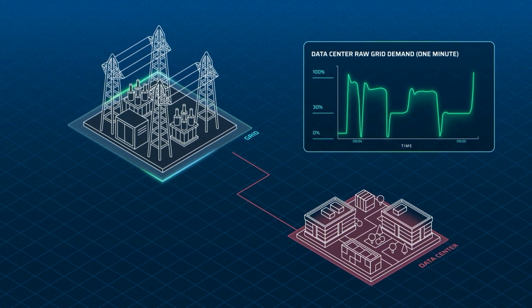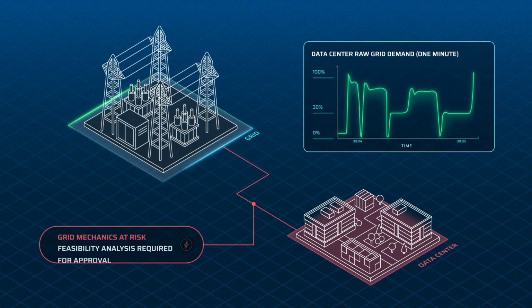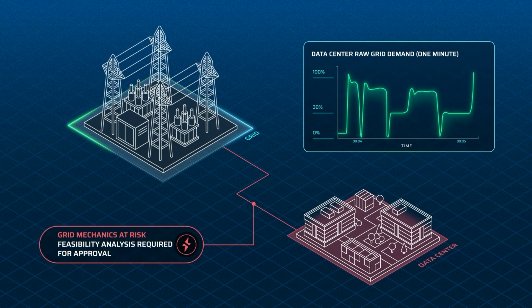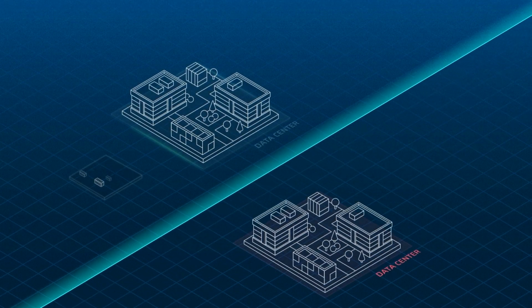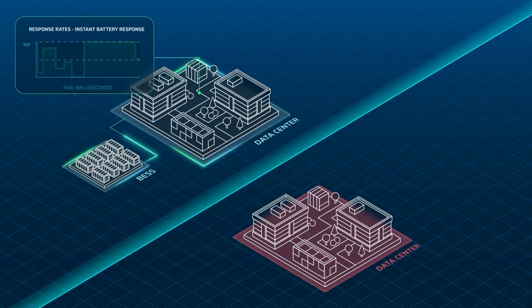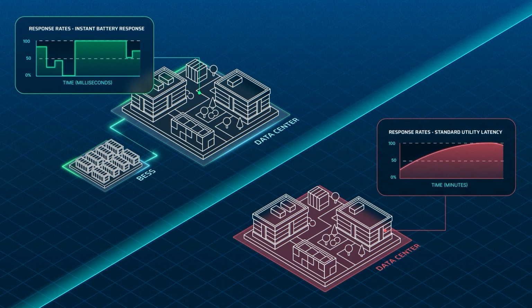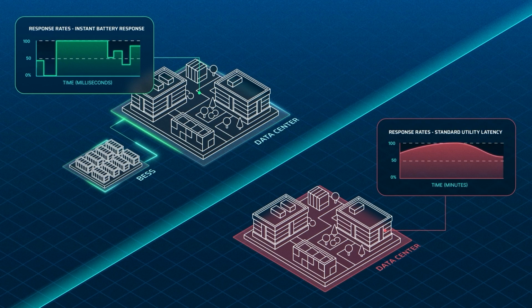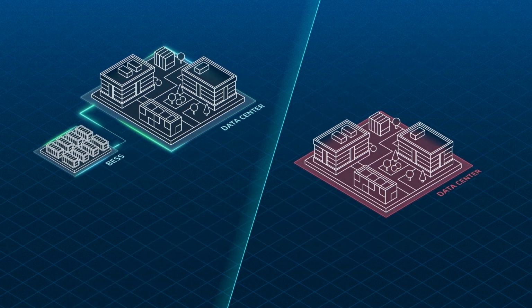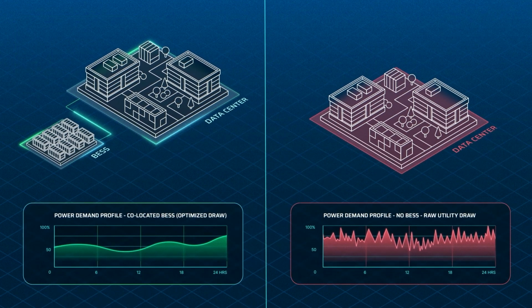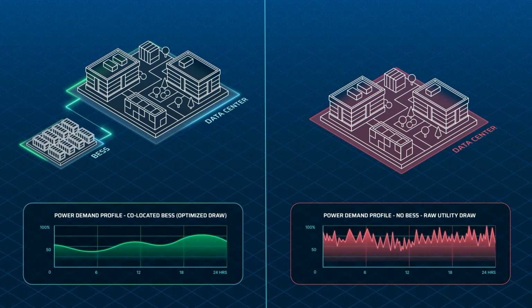This instability doesn't just affect the facility, but also threatens the mechanics of the local grid. This is why utilities are often reluctant to approve massive, volatile loads without first undertaking time-consuming studies and expensive, long-term grid upgrades. By placing battery storage behind the point of interconnection, you introduce an instantaneous response to the site's power profile. The system can ramp up or down in a fraction of a second. By doing this, it absorbs the wild swings in power demand that are unique to data centers.